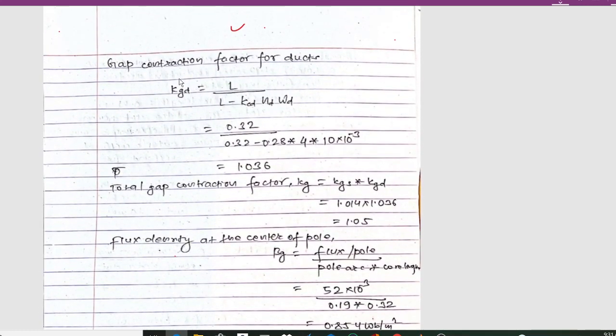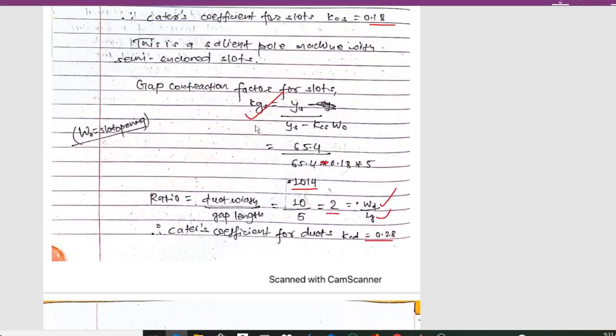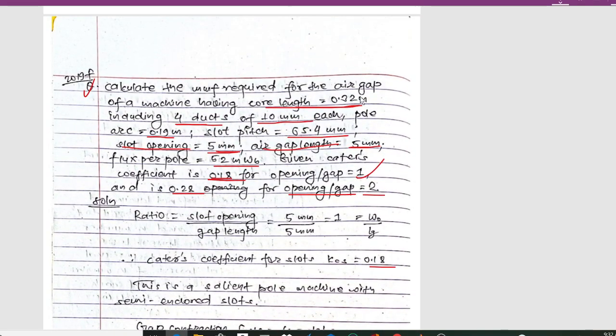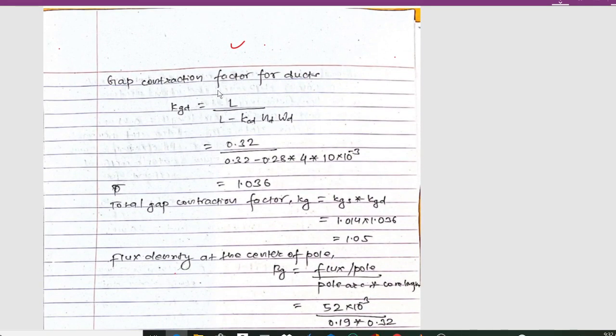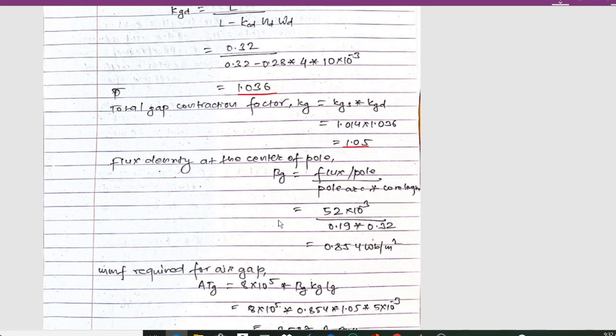The gap contraction factor for the duct is Kgd = l / (l − Kcd × nd × wd), where the core length l = 0.32 m, number of ducts nd = 4, and duct opening wd = 10 mm. This gives gap contraction for duct = 1.036. The total gap contraction factor Kg = Kgs × Kgd = 1.014 × 1.036 = 1.05. Now the flux density at the center of the pole, Bg = flux per pole / (pole arc × core length).